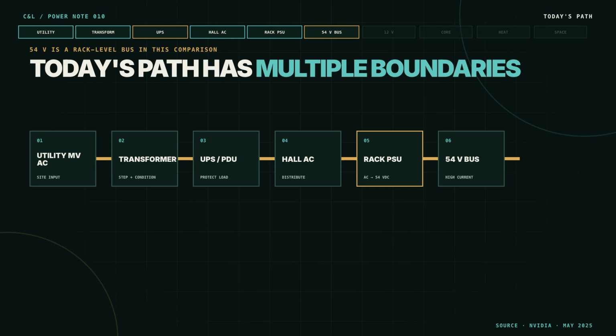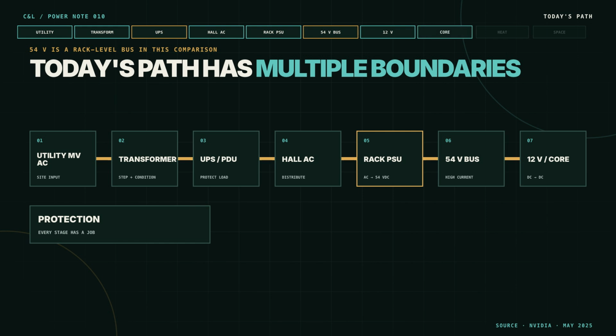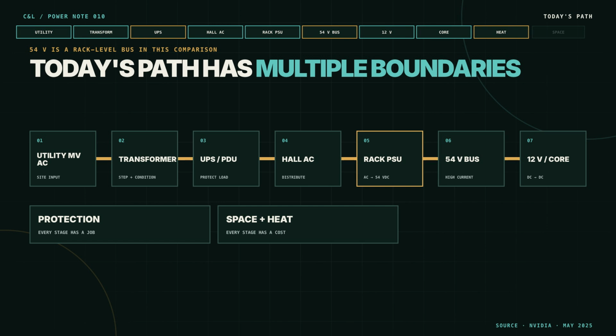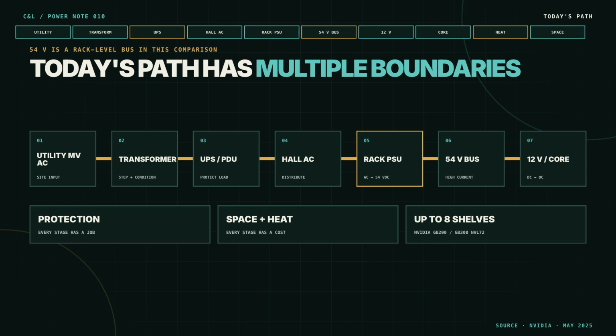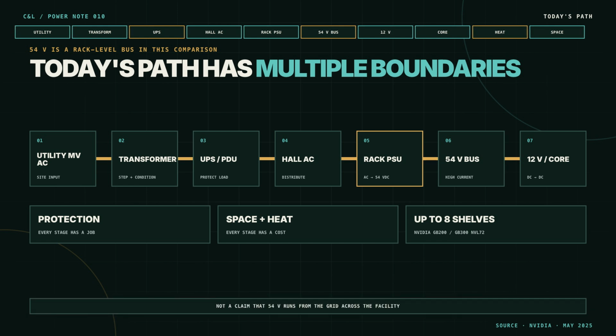Each stage provides protection, regulation, ride-through, isolation, or load response. Each also occupies space, releases heat, and creates an efficiency and reliability boundary. NVIDIA says its current GB200 and GB300 NVL72 systems can use as many as 8 power shelves. Extend that pattern toward a megawatt, and power equipment begins crowding out compute.